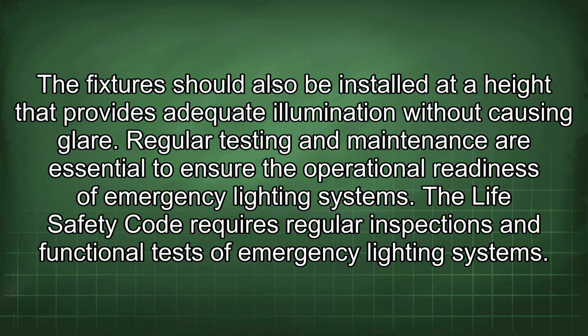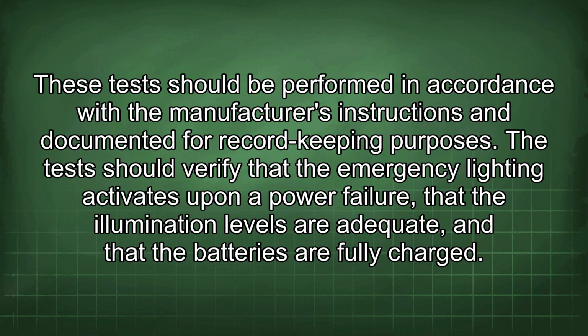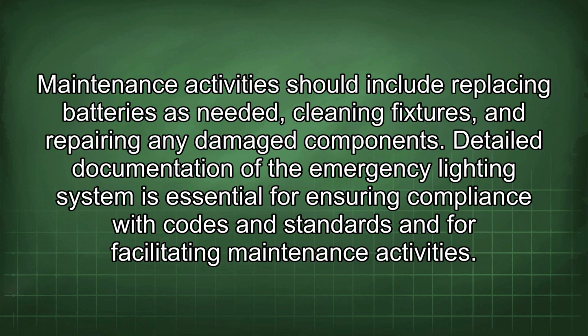Regular testing and maintenance are essential to ensure the operational readiness of emergency lighting systems. The Life Safety Code requires regular inspections and functional tests of emergency lighting systems. These tests should be performed in accordance with the manufacturer's instructions and documented for record-keeping purposes. The test should verify that the emergency lighting activates upon a power failure, that the illumination levels are adequate, and that the batteries are fully charged. Maintenance activities should include replacing batteries as needed, cleaning fixtures, and repairing any damaged components.